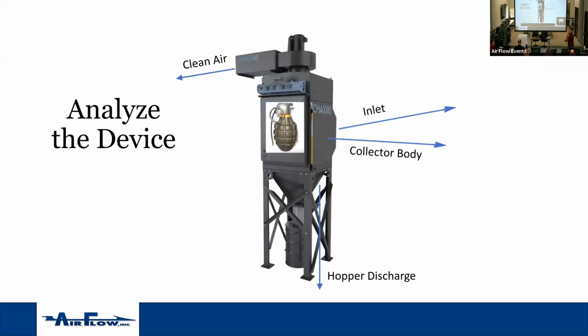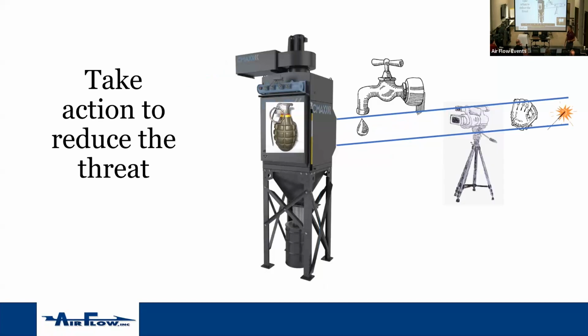So we analyze the collector. This could be any collector. This happens to be a cartridge collector. On your inlet side coming in, you have to stop an explosion from going that way. You have the collector body. You have to contain and direct the explosion, so when it happens, you dictate what happens to that pressure ball and flame ball. And you have to protect the clean air side from the explosion itself going back into the building or outside and affecting people or objects.